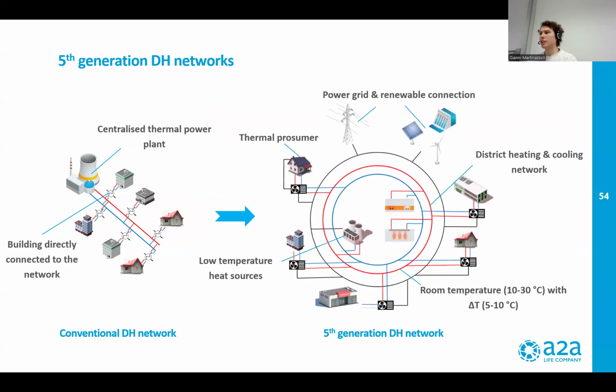In a fifth-generation district heating network, heat is shared at room temperature, typically between 10 and 30 degrees. This makes it possible to use low-temperature heat sources, both natural or derived from waste heat. However, it requires installing decentralized heat pumps at building level in the substation.